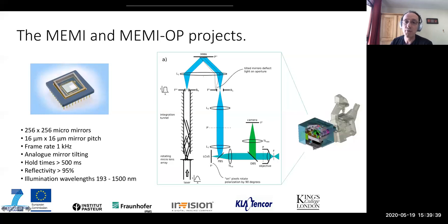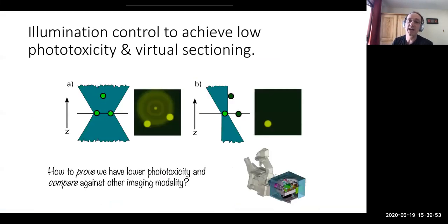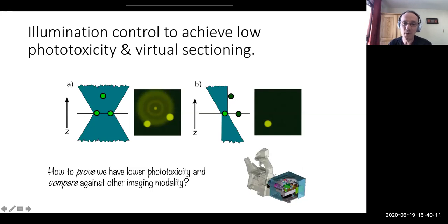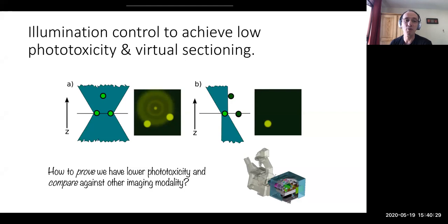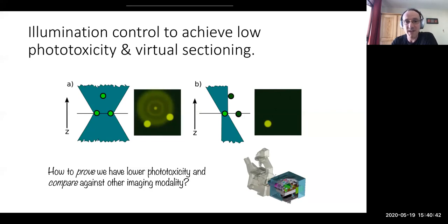Our role in this consortium was to put them at the back of the microscope and run applications with them. These micro mirrors have nice features such as very good reflectivity and analog tilting, giving excellent control over the light shining on our samples. Our goal was to control not only where we would send the light, but also at what angle. With that, we wanted to image very fragile and susceptible-to-light samples with the lowest phototoxicity ever compared to other illumination modalities.